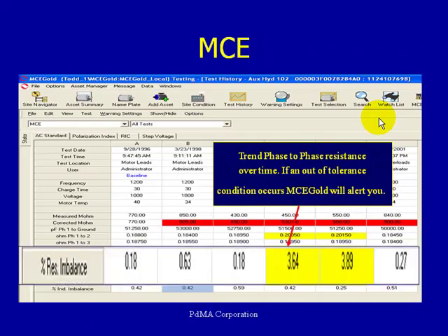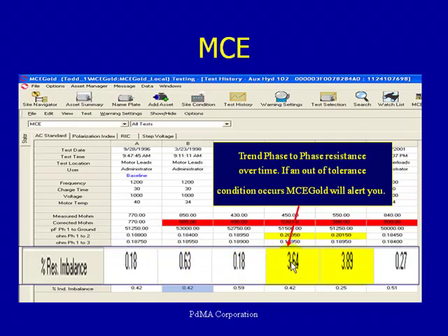Here we look at a situation where we trend phase-to-phase resistance over time. At baseline, our resistive imbalance was 0.18%. Three or four years down the road, it climbed to 3.64% — a clear problem indicating something introduced into the system, possibly a loose connection. This alerts the technician to inspect the motor circuit and restore it to a healthy condition. Once corrections are made, we can see the resistive imbalance reduced back to an acceptable level.